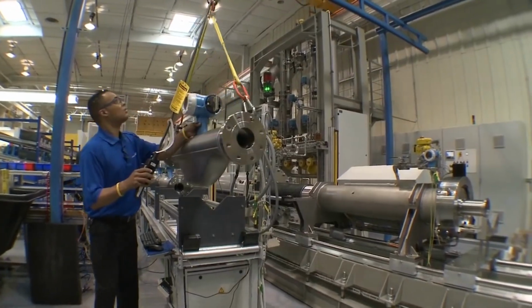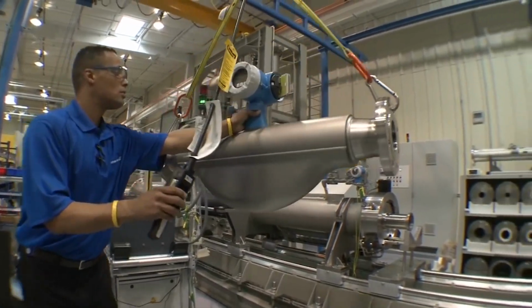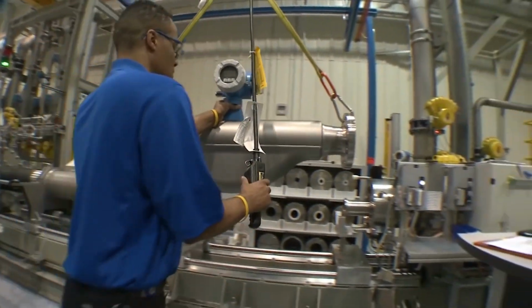Calibration for a lot of customers means a lot of different things, and we have a lot of options to meet whatever those customer needs are. Sometimes it could be as simple as doing a loop check. Other times it could be a verification that the instrument's reading electronically the same way that it's supposed to. And other times it's a full wet calibration where you put a known amount of fluid through, say, a flow meter and make sure that flow meter is reading the same amount.